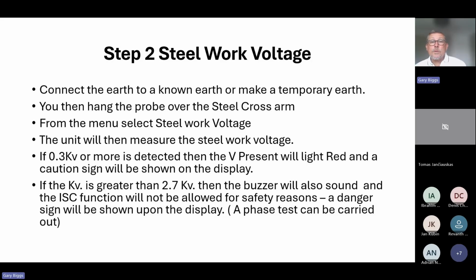You know that if the voltage is greater than 2.7 kV, then you need to take due precautions, and it will be treated as a live situation. A danger sign is shown upon the display and a phase test can be carried out. So we'll be getting to the phase test in a minute.